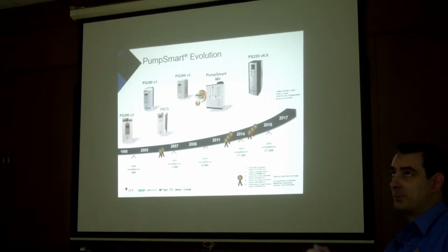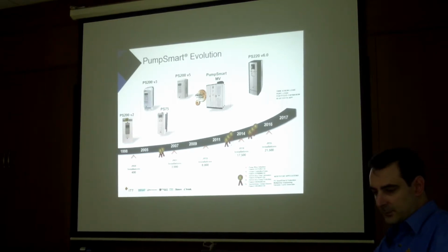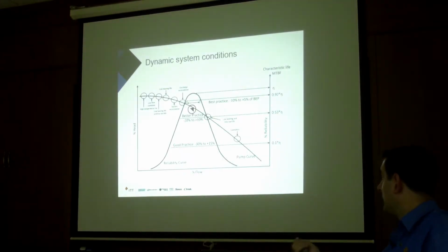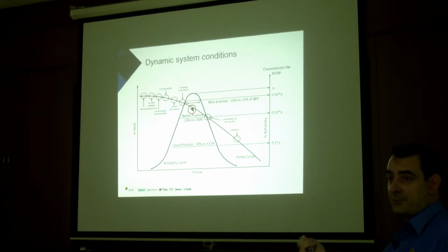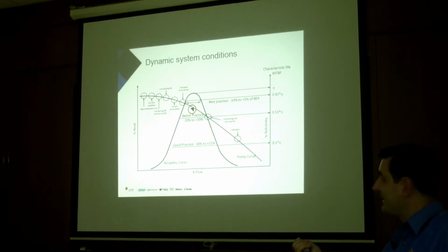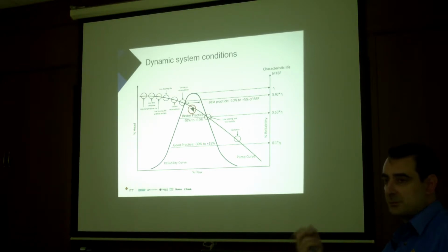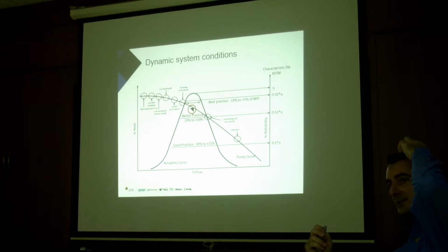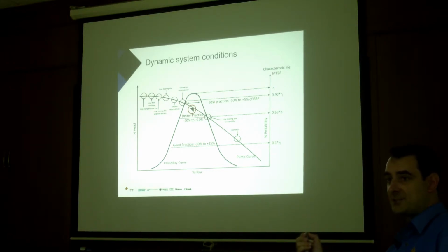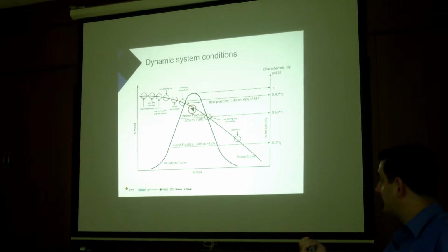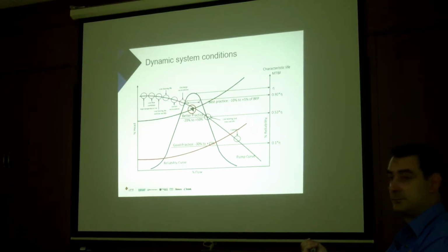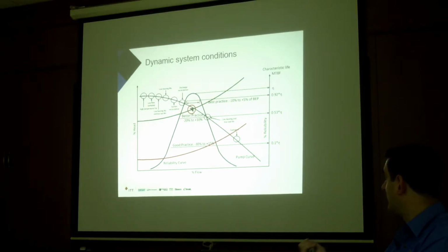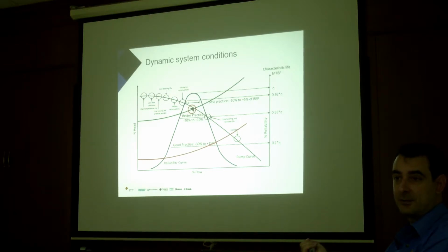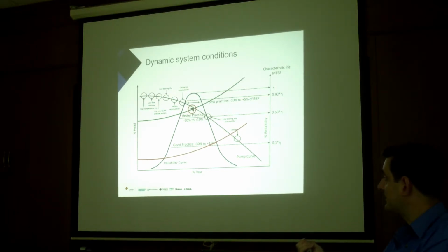The reason we can use the best efficiency point is because it tells us that we're here. If they first change the pipe and then they start operating here, they just throttle back. Now if they're here, there's nothing much we can do. All we can do is increase speed. But still, we can maybe look at the application and understand how we can use our features to be of benefit to them. In Vopak terminal, their problem was they always operate here. So they will turn the pump on. They will see that they're being told you're operating at maybe 130% best efficiency point. So then they just keep throttling back until they see 110%.